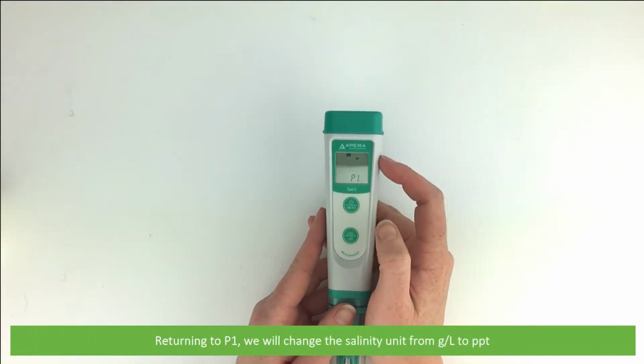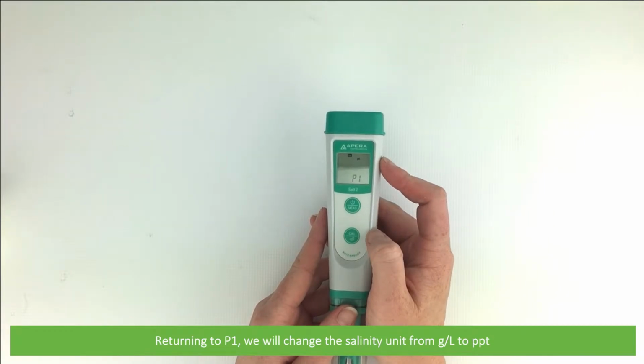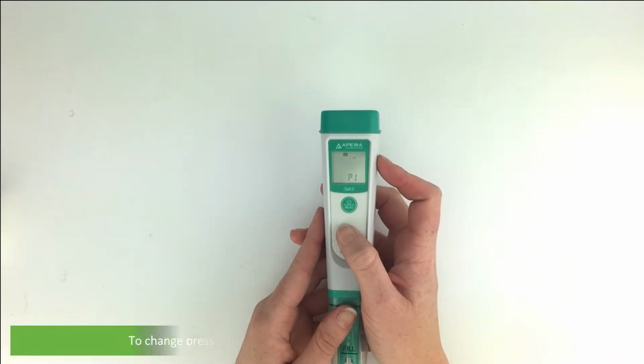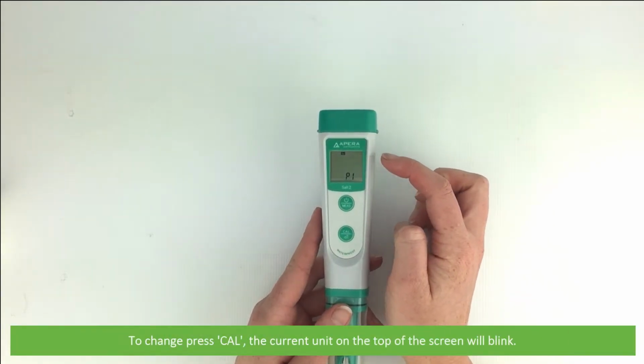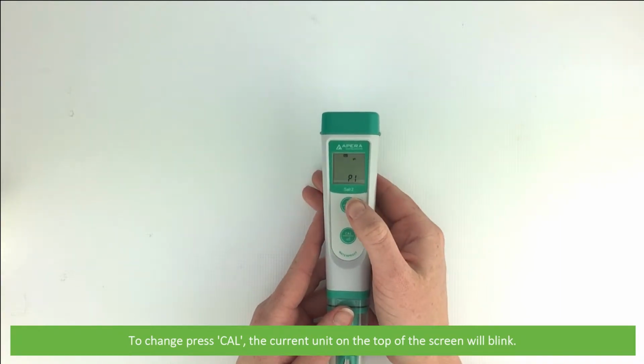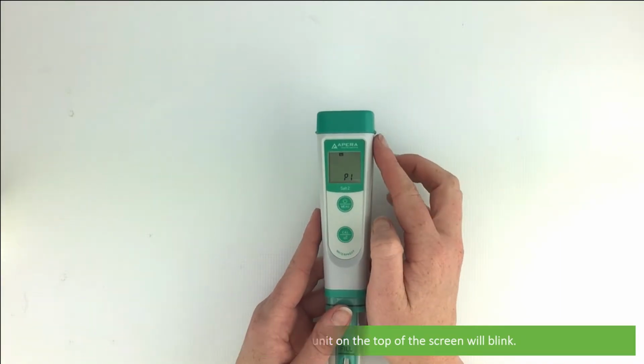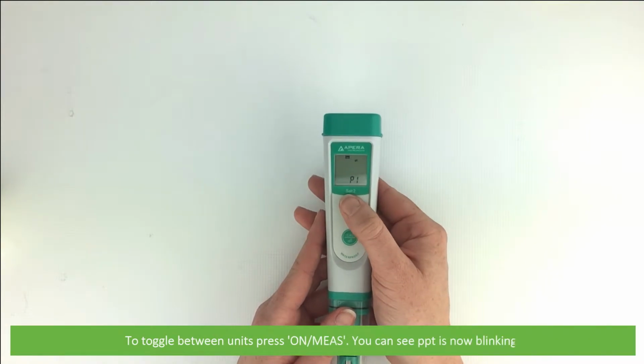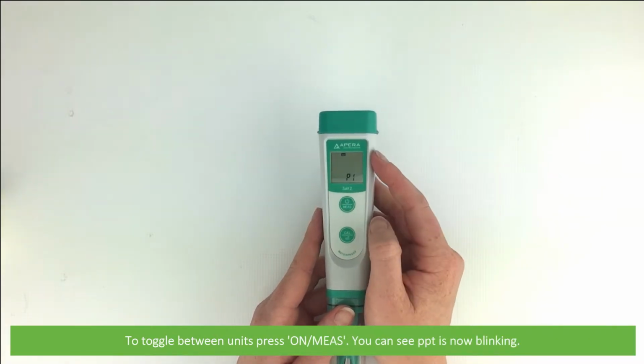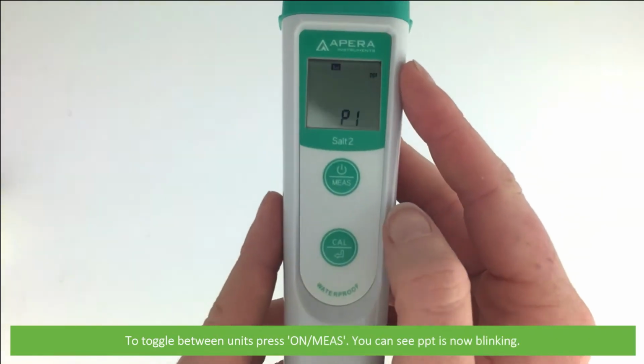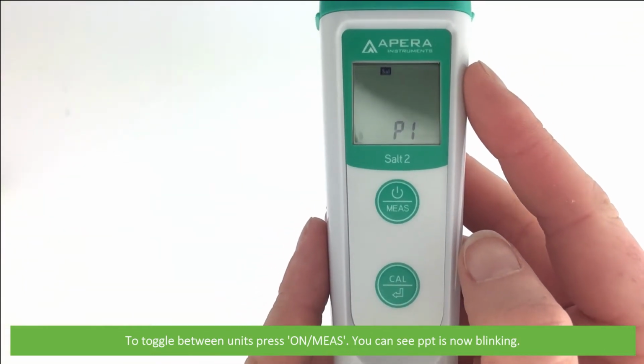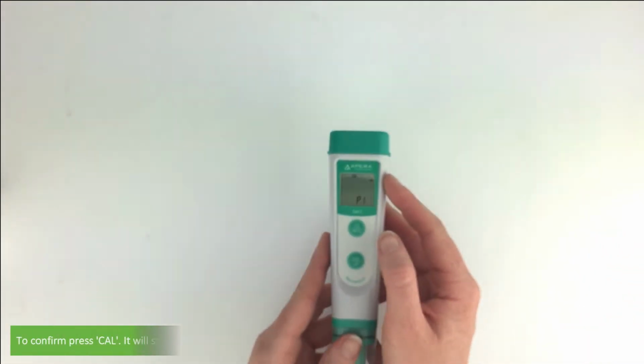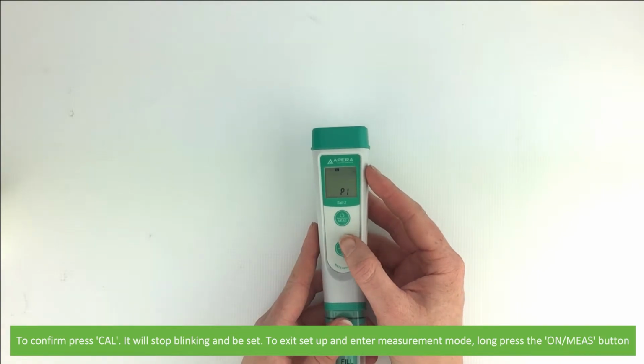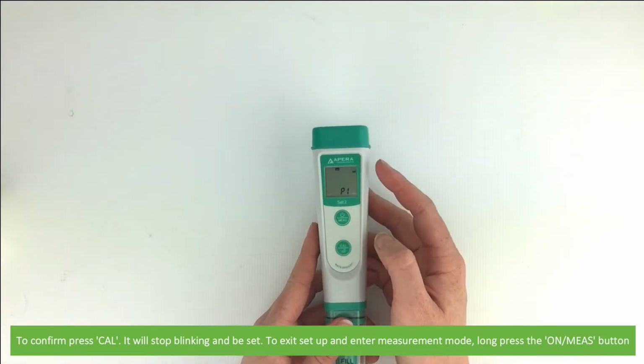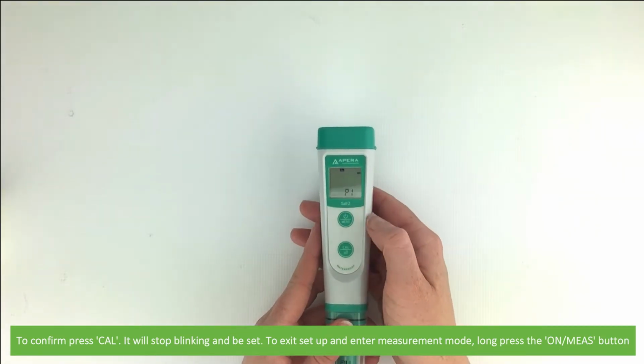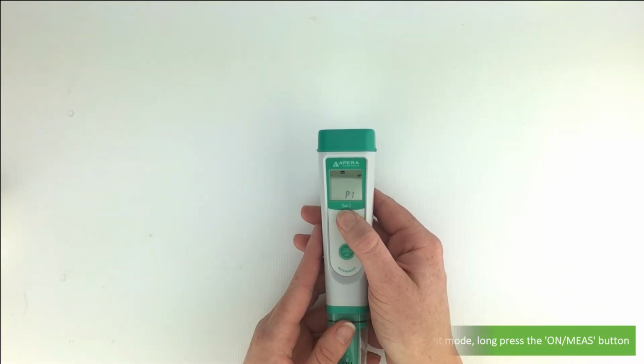Returning to P1, we will change our salinity unit from grams per litre to parts per thousand. To change, press Cal. The current unit on the top of the screen will start to blink. To toggle between the 2 units, press on/measure. You can see PPT is now blinking. To confirm, press Cal. It will stop blinking and be set. To exit the setup and enter measurement mode, long press the on/measure button.